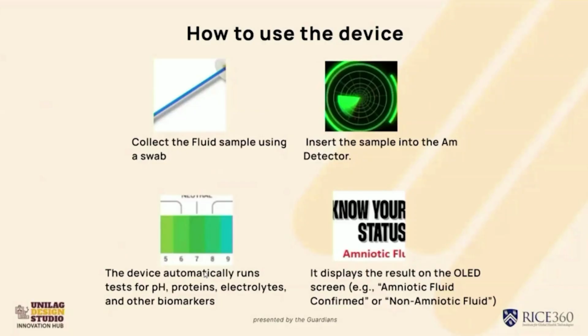This is how the device works. This is its working principle. When it detects the fluid, it scans for the pH. There is a range for amniotic fluid pH, which is between 7 to 7.5. If it is a yes, it does a conductivity test for accuracy. If the conductivity is high, it does a dryness check. The dryness check is because of the fern effect of the amniotic fluid, which takes a longer time to dry up. If that is a yes, then it confirms that that fluid is amniotic fluid, and it displays a possible PPROM, helping the mother know that she needs to get to the hospital to get checked.